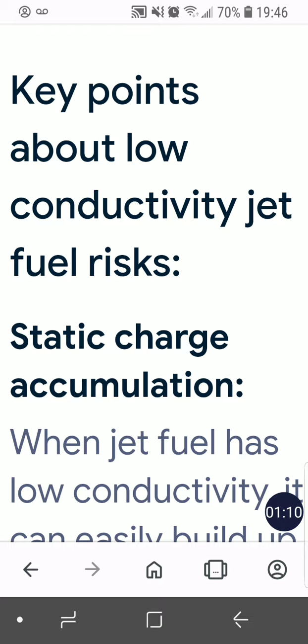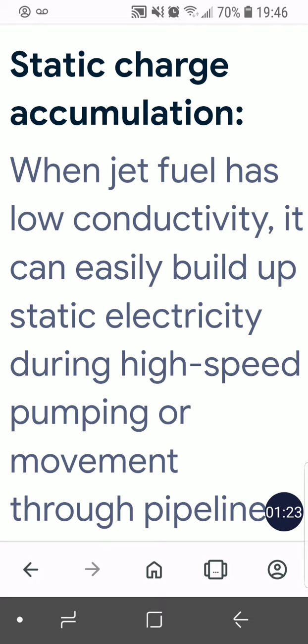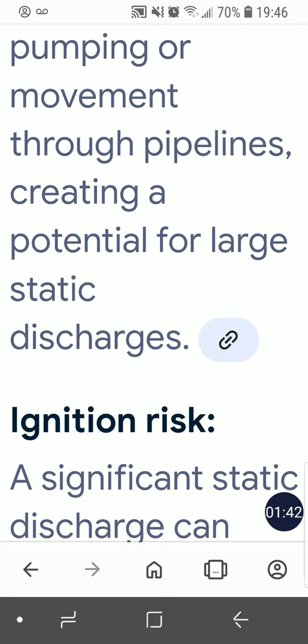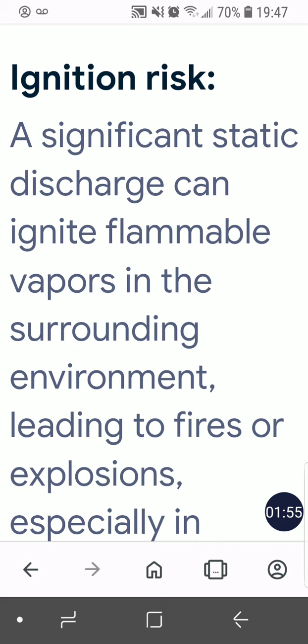So again, the key point to remember is when your fuel has low conductivity, it has a high risk of building static electricity, which will then cause sparks during pumping or movement or transfer of fuel in pipelines, and those sparks can ignite flammable vapors, which will then cause explosions and fires.